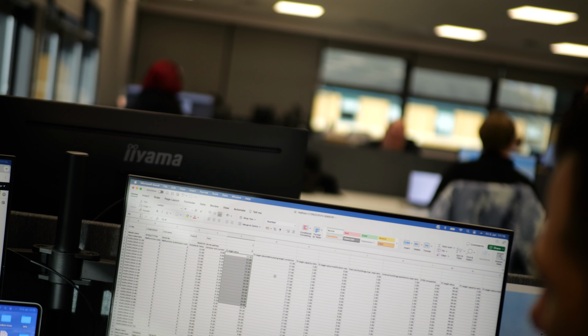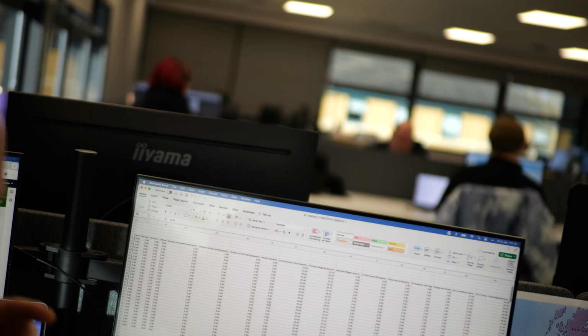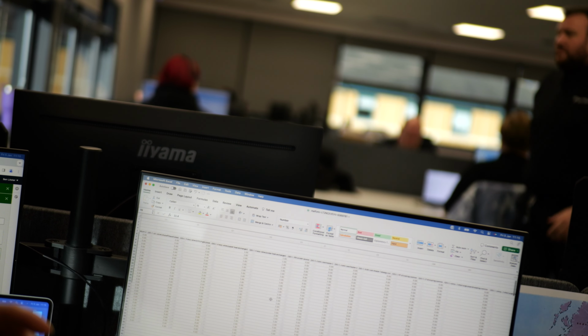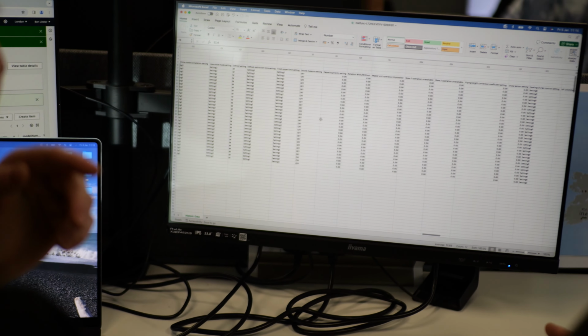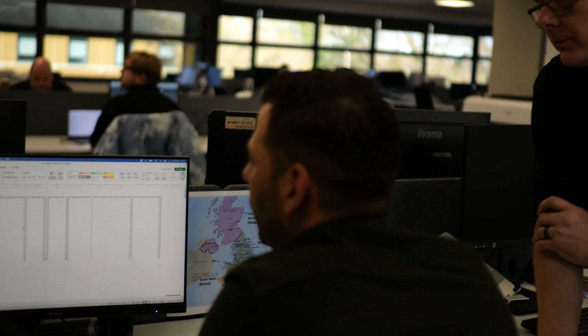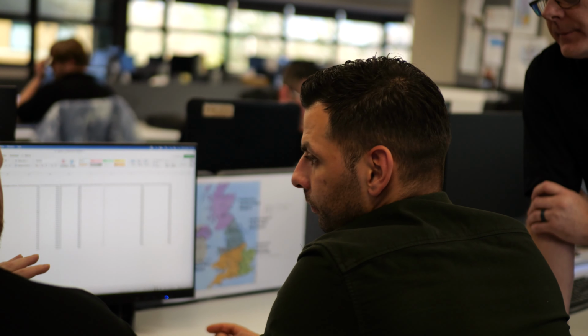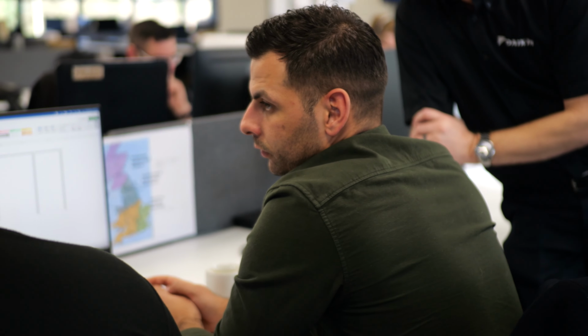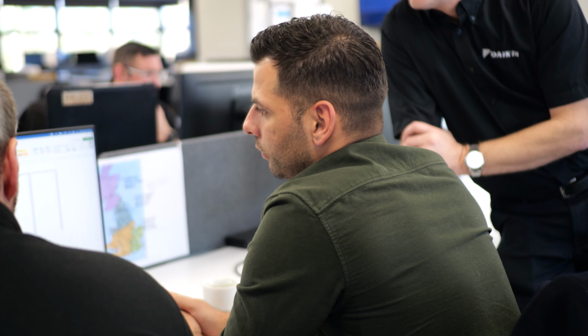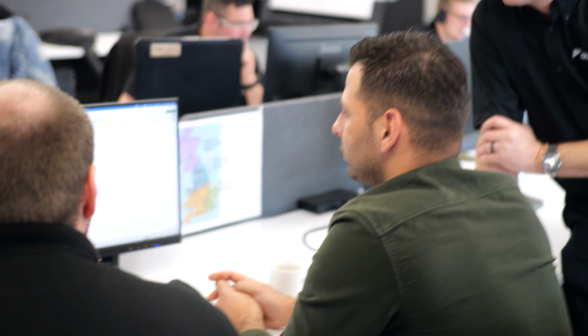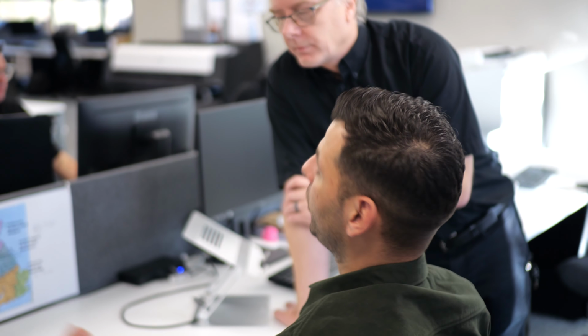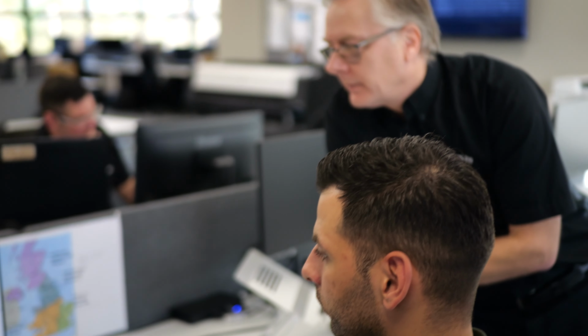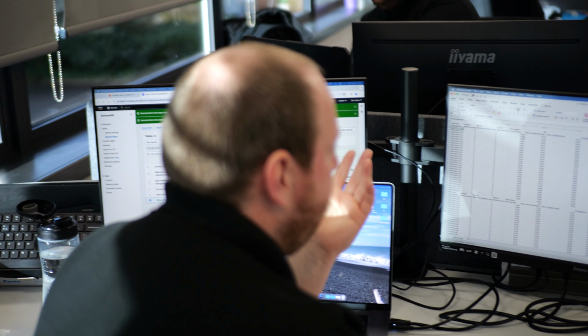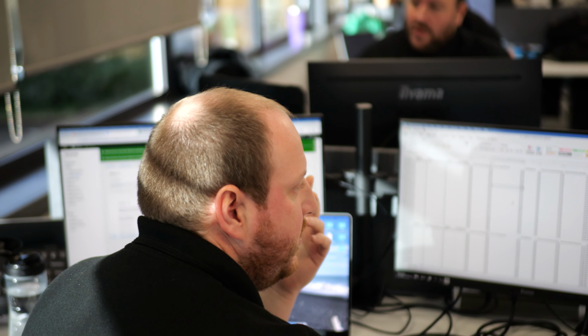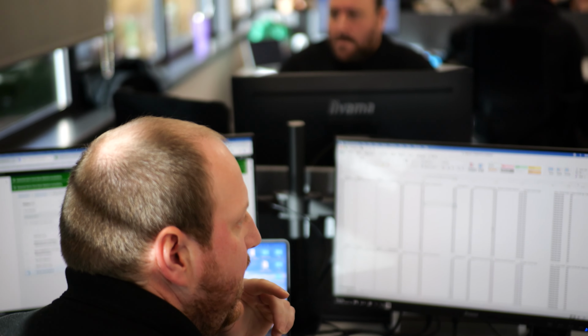But when the systems are running, you can see all its target evaporation temperatures, condensing temperatures. So you can scroll across, and across there's a lot of data. Wow. That's just the outdoor systems right away. But this is something that can be looked at by the engineer to give an answer of, well, your system has been down for the last 6 weeks. You can also see if anyone's put certain settings in that can change how the actual outdoor unit runs, so if they change the level difference, the 90 metre settings, any condensing target settings. And this goes back to almost knowing what you're looking at. But then we also have all of the indoor data as well, so we can see suction temperatures, minute by minute temperatures of everything, expansion valve openings, set points.